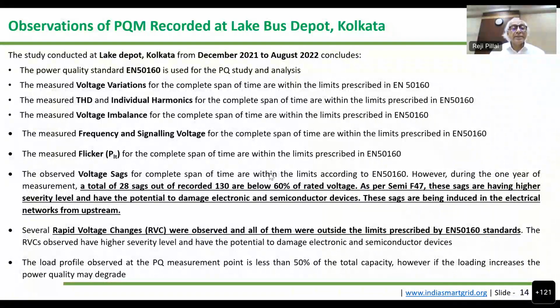The voltage sags, here again, we noticed most of them are within the limits according to EN 50160, but there are some voltage sags, actually 28 sags out of 130 sags, that were below 60% of the normal voltage, which as per SEMI F47 have potential to damage electronic and semiconductor devices.